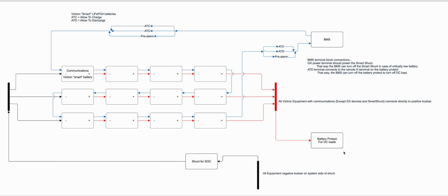The Victron Battery Protect is basically just a fancy solid state relay, or you could even use a simple DC contactor. And this BMS has an ATD port, allowed to discharge port. And when everything's okay to discharge, it puts battery voltage to that ATD port. So then that ATD port powers the remote on-off terminal on the Battery Protect or a solid state relay or a mechanical contactor, and that allows the DC load to run. And then if the BMS hears from the batteries that they need to stop discharging, then it will immediately interrupt that battery voltage to here. Then this will turn off the DC load, and that protects your batteries from over discharge.